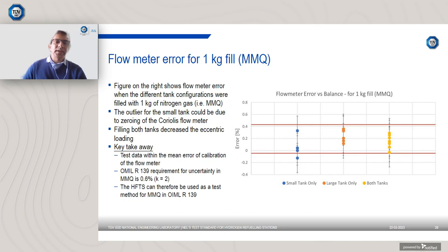The data shown here is for a 1 kilogram fill, which is the minimum measured quantity as specified in OIML R139. And what we found during the testing was that it was best to fill both tanks with nitrogen gas, simply because that way you minimize the impact of eccentric loading. We especially saw this effect when we were putting in reference weights at different locations on the test rig.